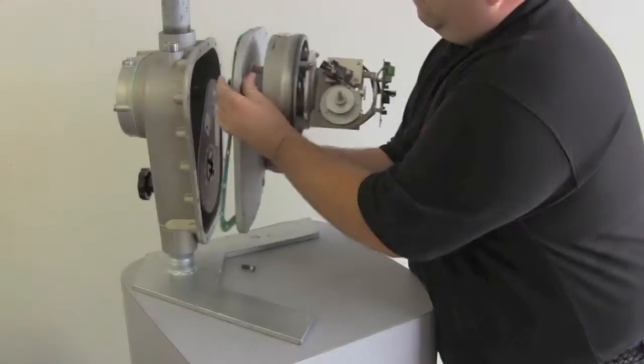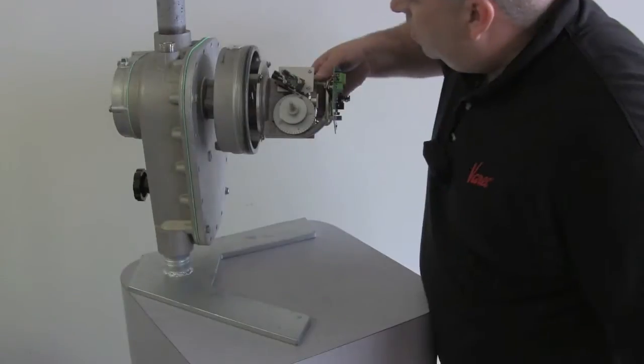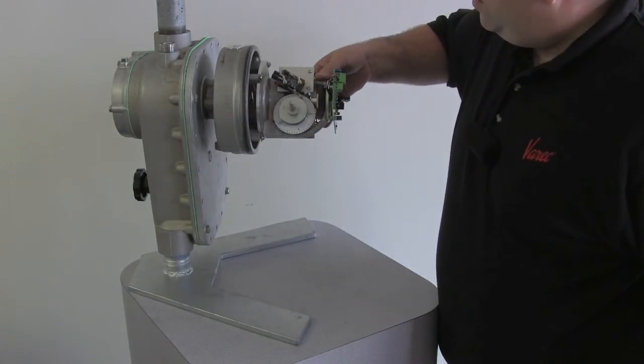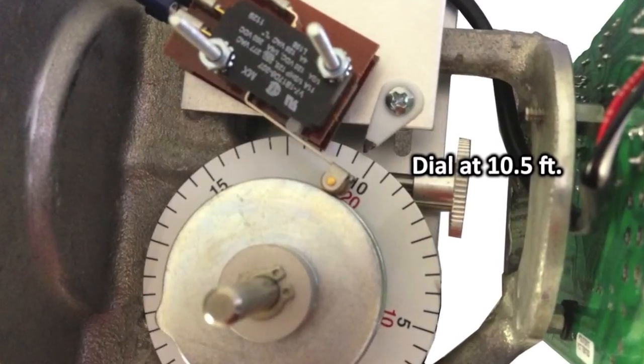Reinstall the transmitter on the back of the gauge. Check the transmitter shaft to ensure that the coupling is engaged. The two should now match to a quarter of an inch.